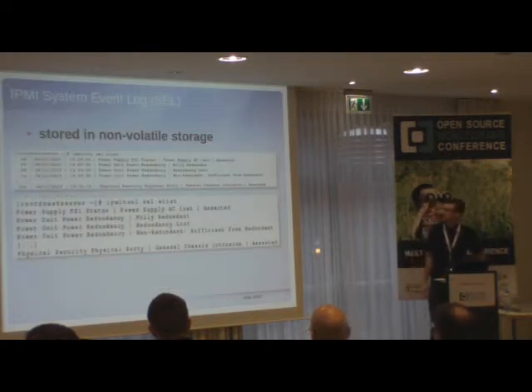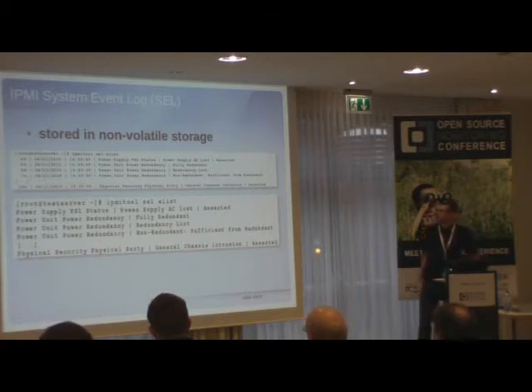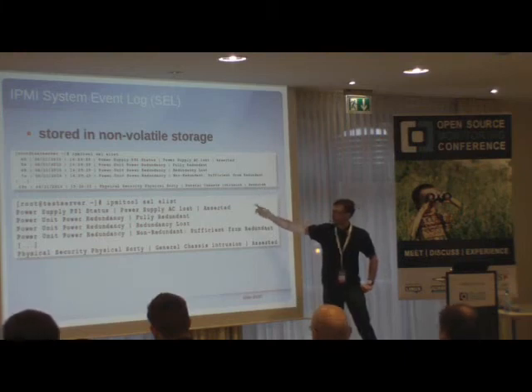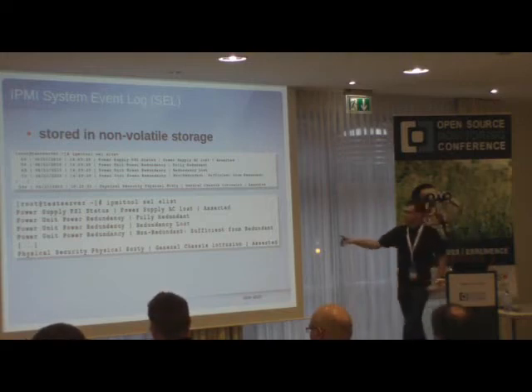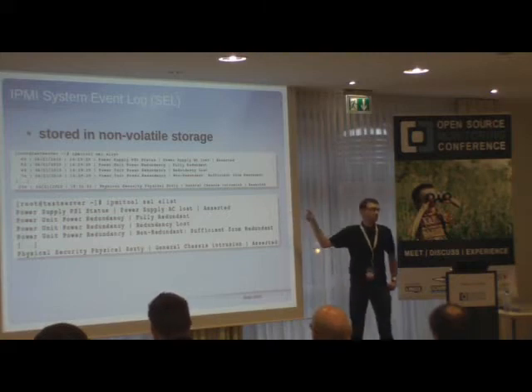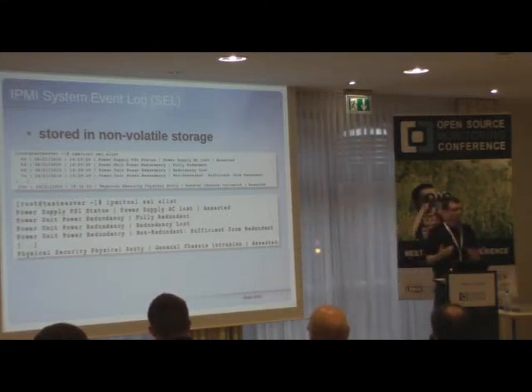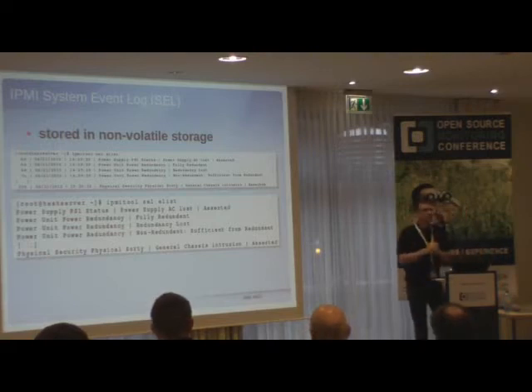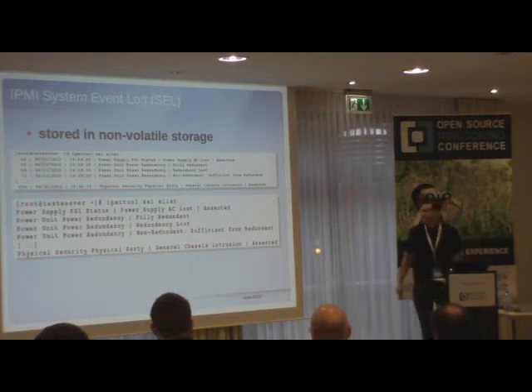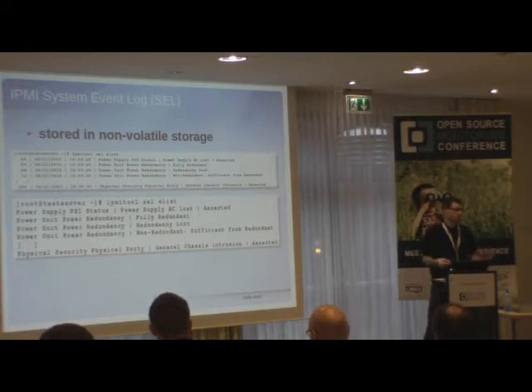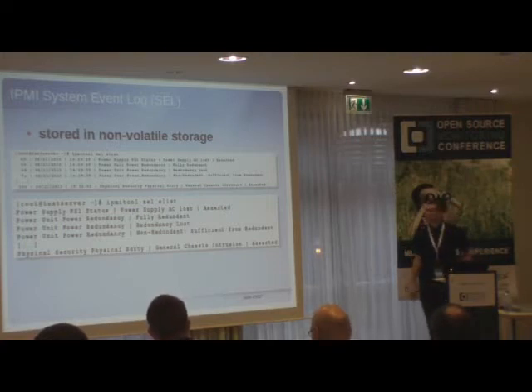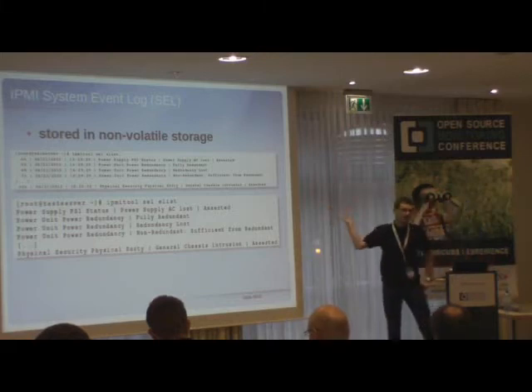As mentioned before, you also have the hardware event log — the System Event Log. Here you can see information such as whether power redundancy has been lost. You can use different tools like ipmitool or the FreeIPMI suite to read this system event log. An important note: depending on your server, you get a lot of messages when you boot the server, or when you do kernel updates and reboot. Or if you have ECC errors, the log fills up. The log holds about 10,000 lines, so it can get full. When it's full, no additional events are logged, so it's good to check it regularly, save the output, and then clear it.